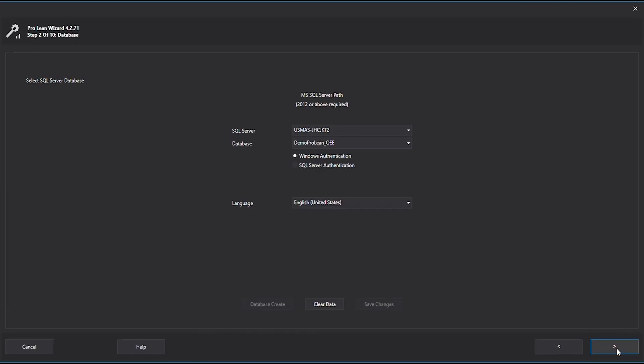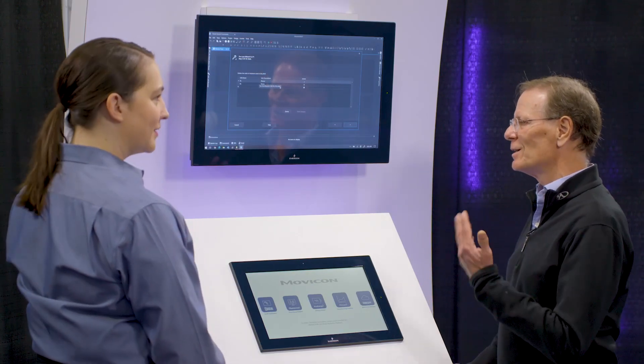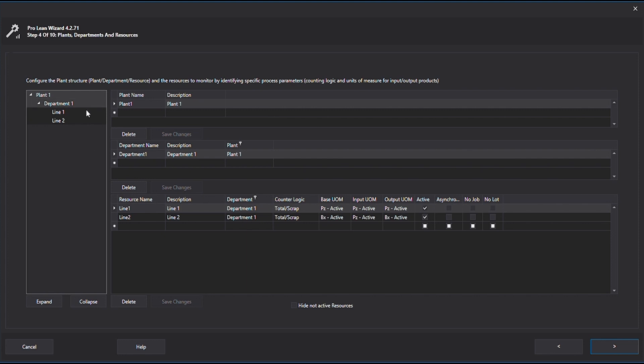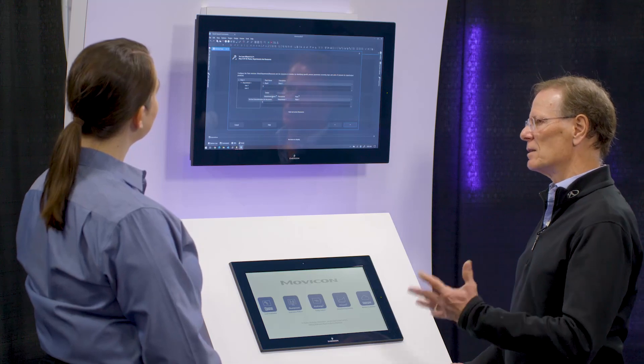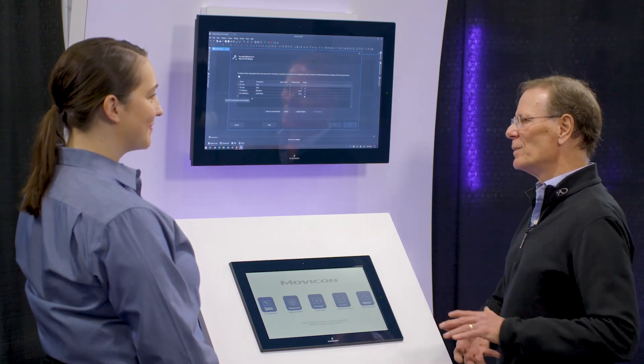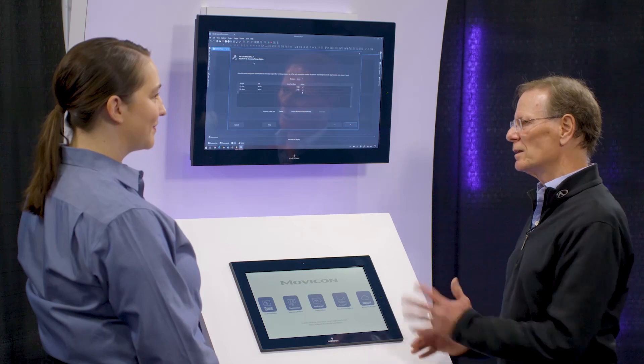I hit next: what's the database — where is the data going to be stored? Next question: what are my units of measure — am I making pieces, am I making boxes? Third set of questions: what are my lines, my plant, my departments, so I can navigate the hierarchy of OEE machines and get summary reports. The next set is around what am I producing and what recipes are associated with that, which tells the equipment what's coming next and how to set up its parameters. Then I tie the recipes to the equipment so each piece knows which product it's involved in.